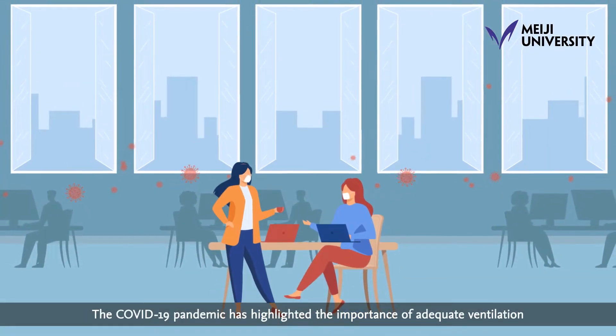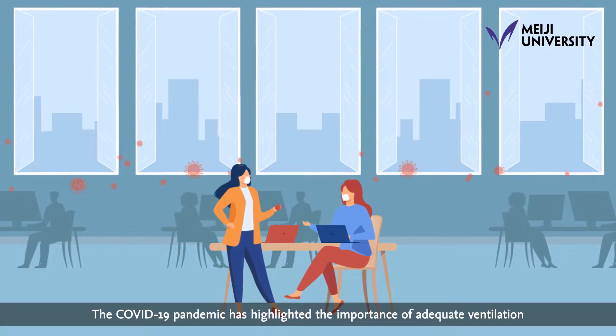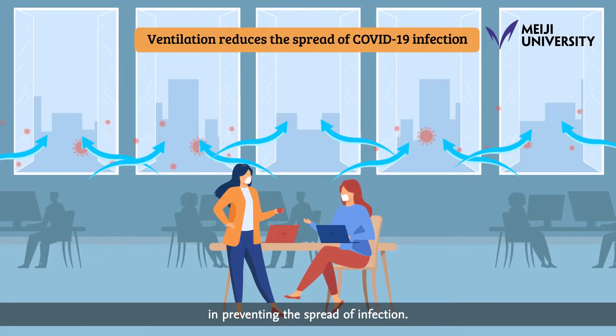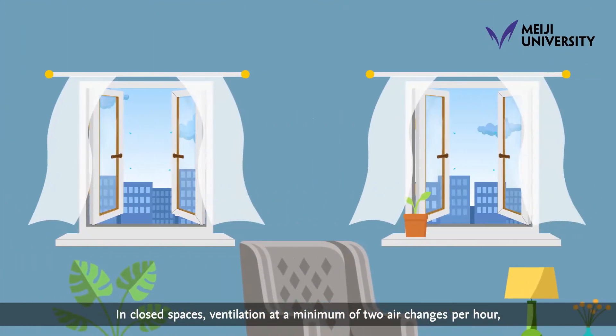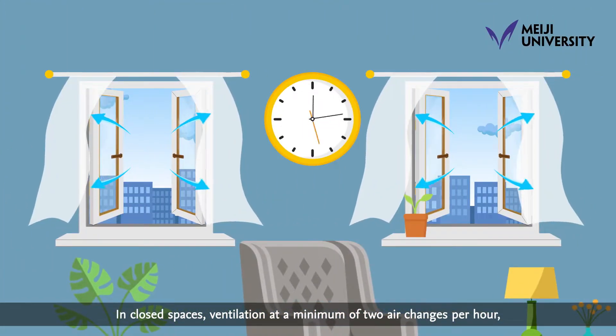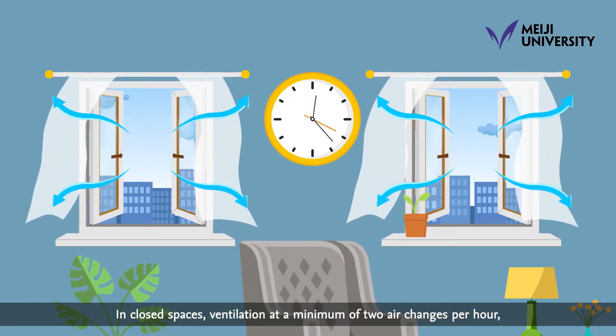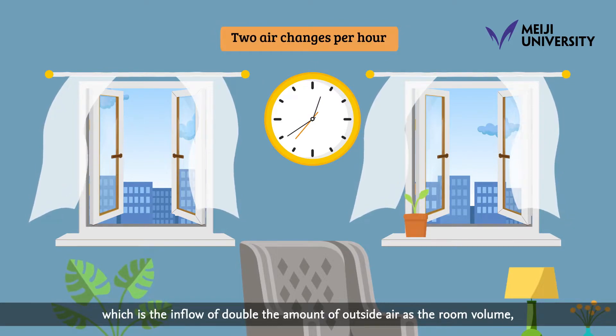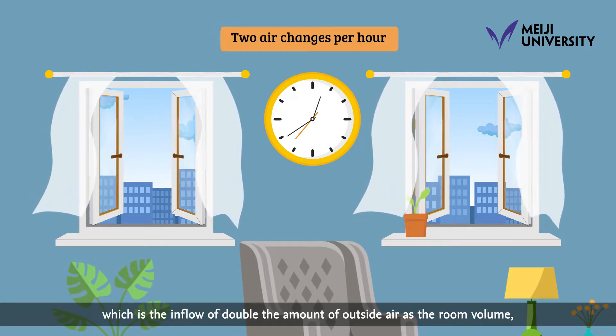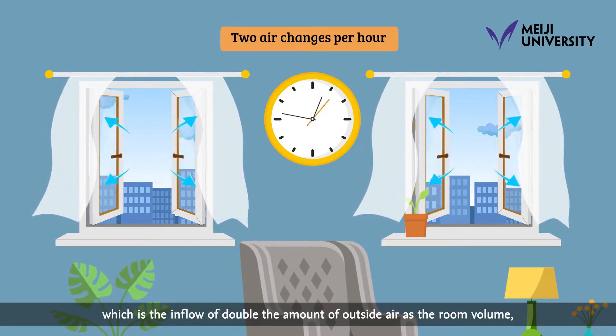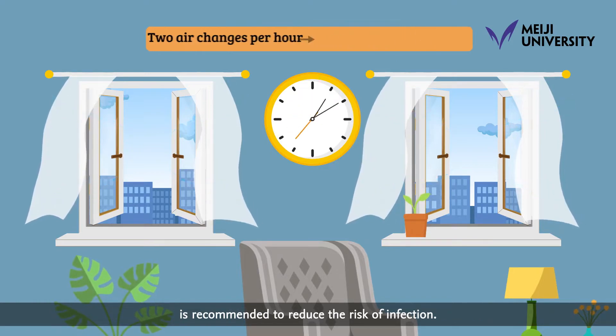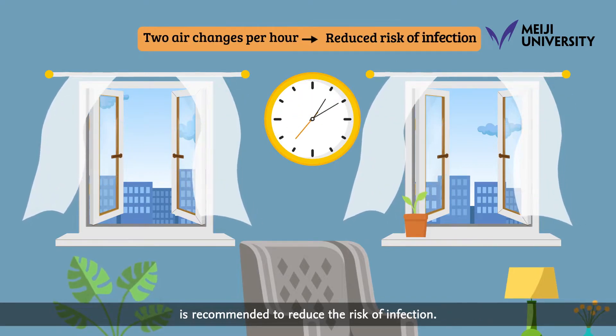The COVID-19 pandemic has highlighted the importance of adequate ventilation in preventing the spread of infection. In closed spaces, ventilation at a minimum of two air changes per hour, which is the inflow of double the amount of outside air as the room volume, is recommended to reduce the risk of infection.